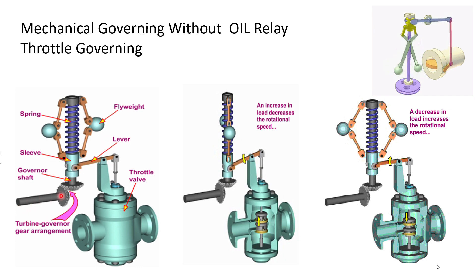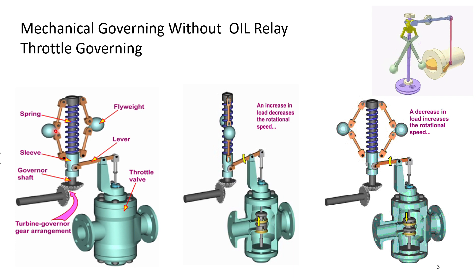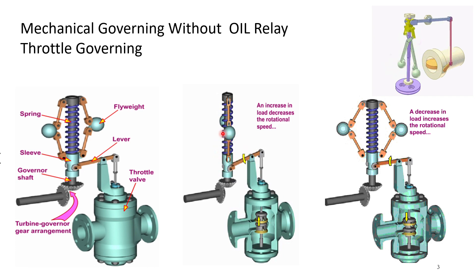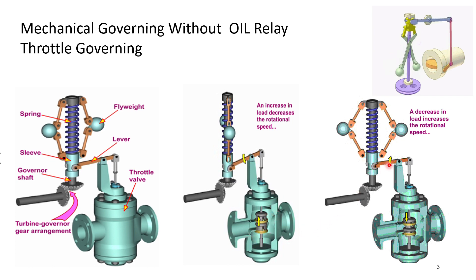This is your turbine shaft through the gear. This spindle is connected and two fly balls are mounted here. When the turbine speed goes up, the fly balls will start moving out, this sleeve will move up, and then it will close the valve inside. When the turbine speed decreases, this valve will start to go inside, and as a result this sleeve will go down and it will open the steam valve to pass more steam.